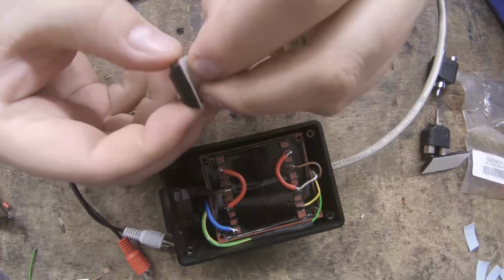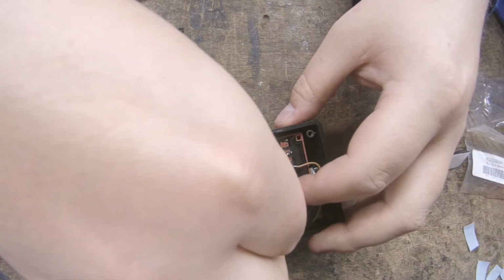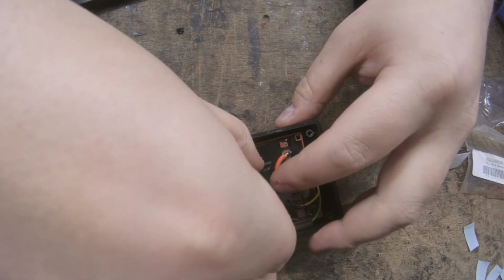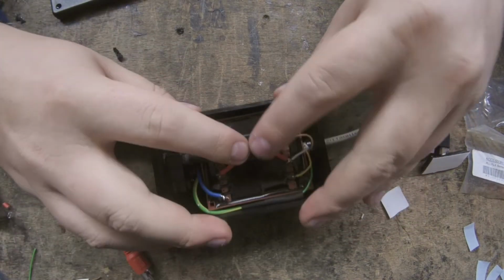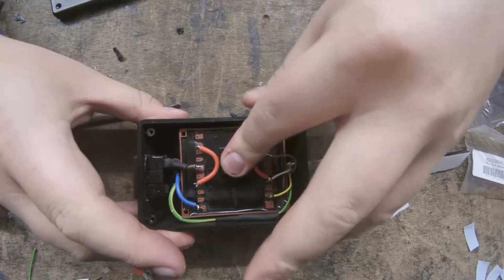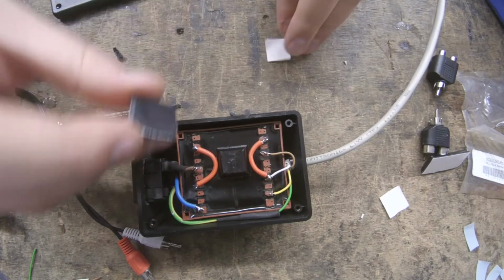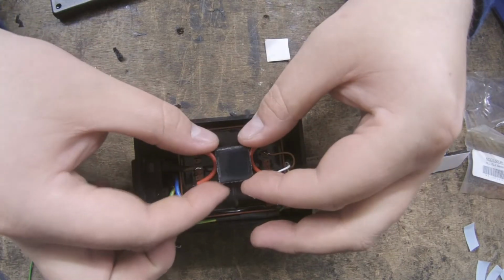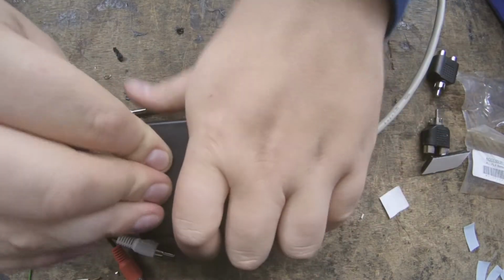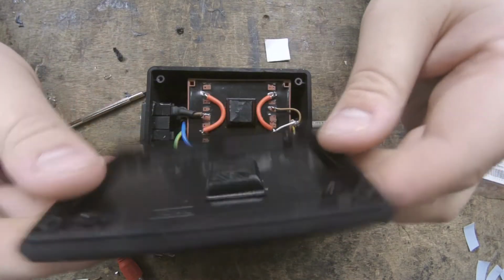To stop the transformer rattling around inside, we need a self-adhesive rubber pad on the transformer and another one on the lid of the enclosure to press against it. To get everything lined up properly, we can balance the lid's rubber pad sticky side up on the transformer's rubber pad. Then when we carefully attach the lid, it will stick to the pad very nicely, giving a very tight fit for the lid.